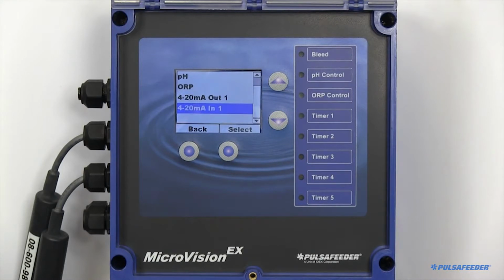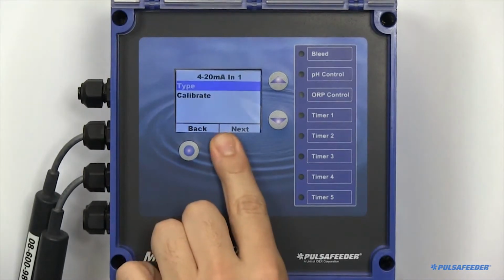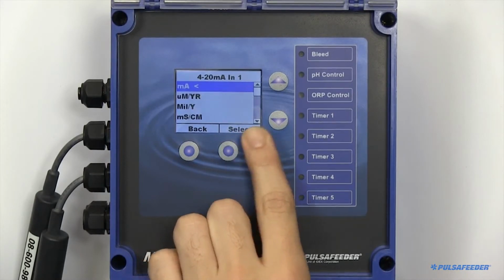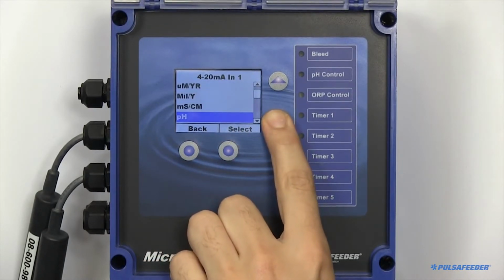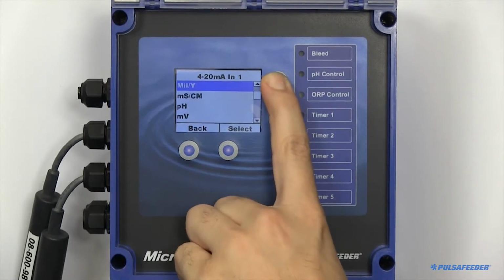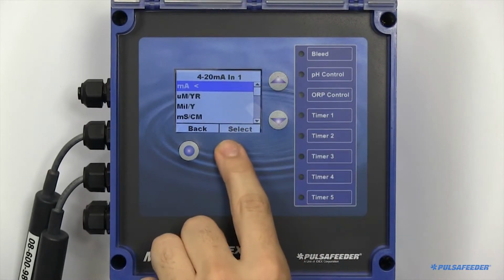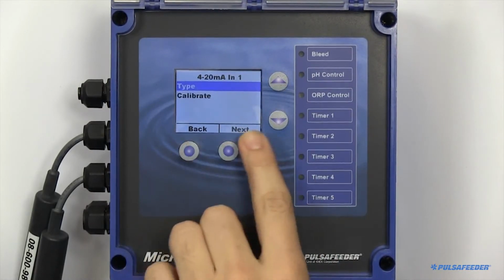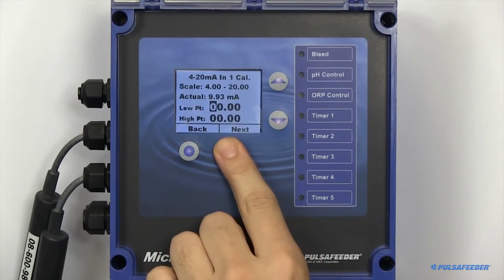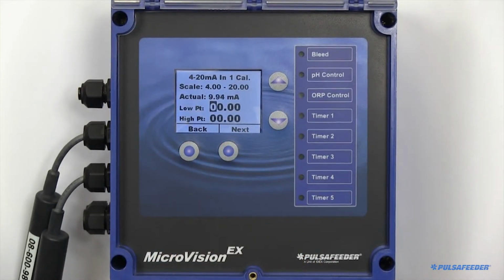Four to 20 input boards can also be configured. It's very similar to configuring your 4 to 20 output. First, you must specify the type. After specifying your type, you then need to calibrate the board. You may need buffer solutions to perform this. The top row indicates your low point. The bottom row is the high point. You will need 2 buffer solutions.